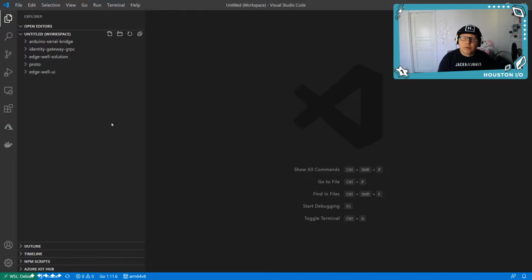So what I started with: we ordered a hydrostatic pressure sensor from China. It has a 10 meter long cord, and it's optimized to measure the water level, or the liquid level, from the pressure it senses when you lower it down to the bottom. It works as RS485, so the current loop technology. It has a 4-20 milliamp current going, and that can be translated to a value.